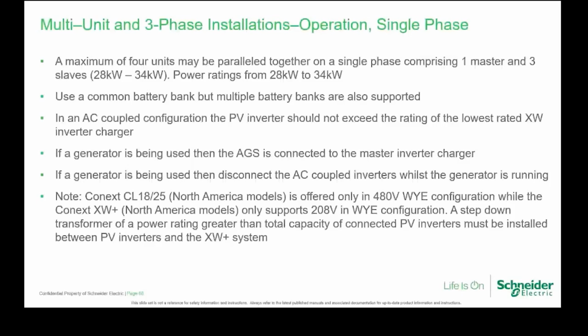Now, the Conext CL18/25, which is the North American model, is only offered in the 480 volts WYE configuration, but the XW Plus only supports 208 volts in WYE configuration, so you might require a step-down transformer of a power rating greater than the total capacity of connected PV inverters. That must be connected between the PV inverters and the XW Plus system.